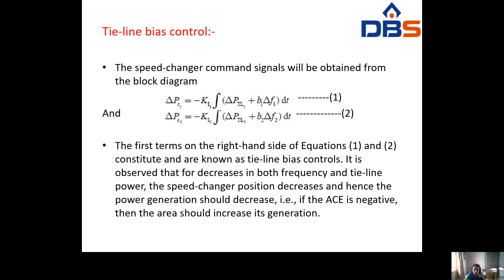Next, tie-line bias control: the speed changer command signal is obtained from the block diagram as delta PC1 equals minus KI1 times the integral of (delta PTL1 plus B1 times delta F1) dt, and delta PC2 equals minus KI2 times the integral of (delta PTL2 plus B2 times delta F2) dt (equation 2). The first terms on the right-hand side constitute tie-line bias control. For decreasing frequency and tie-line power, speed changer position decreases, reducing power generation; if the ACE is negative, the area should increase its generation.